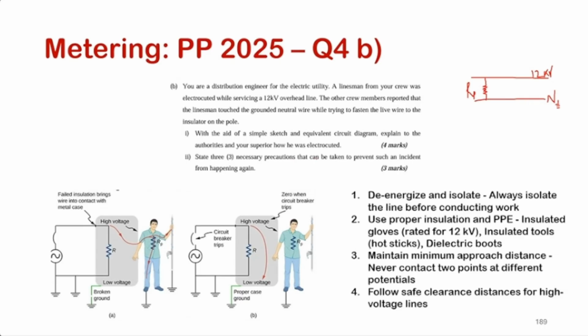Then these three necessary precautions will be taken to prevent such an incident from happening again. The first thing is to de-energize and isolate. You must never work on energized circuits. Sometimes you have to, but you try your best to work on non-energized circuits. So obviously the first thing is to de-energize the circuit and do the work. The next thing is to use proper insulation and proper PPE, such as insulated gloves, insulated tools, and hot sticks, like you see us using on the line, and dielectric boots. Obviously, you also maintain a minimum clearance between your line and grounded neutrals or grounded conductors, because otherwise that will create a potential and you will get shocked.